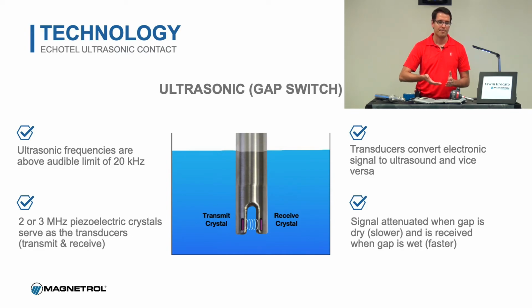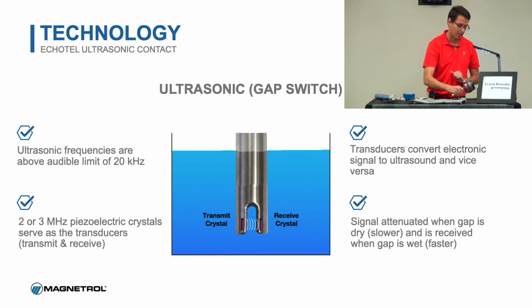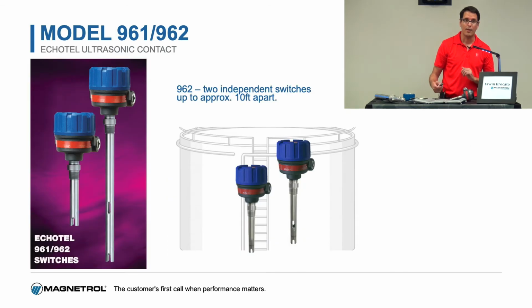So that can be a high level switch. If the level comes up to the sensor, to the gap, let's say the switch is installed sideways, the level comes up to here, it'll close the gap and the relay will energize. Or vice versa, you can set one of the little jumpers on here for a low level switch. So the relay is always energized because the tank is full. But if the level drops below, the gap is now dry and it will de-energize the relay on the particular application. So that's how that one works.